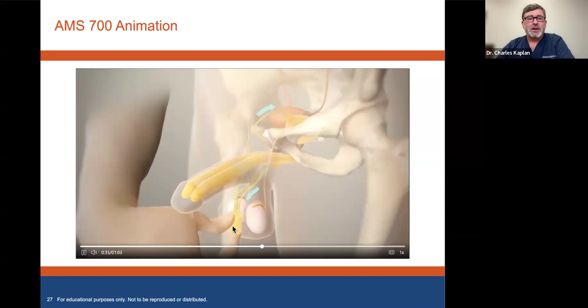So the reason the pump is so much bigger for the penile implant is because there's so much more fluid that needs to be transferred to the cylinders. The amount of fluid for a cuff is minimal compared to the volume that needs to be used to inflate the cylinder. So the pump has to be bigger. Otherwise, it would take forever to pump the device up.